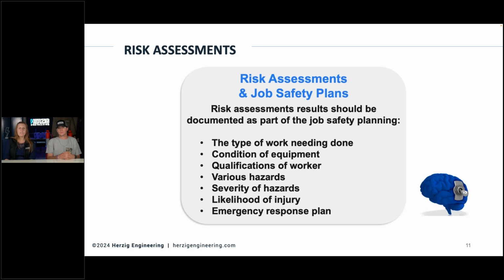And then the severity can change as well. If you're just operating a breaker and everything's installed properly, all the coverings are in place, and the full and complete dead front is still in place, the severity of what you're facing is more than likely lessened. Even if something goes wrong, that properly installed, properly maintained dead front with no openings is going to contain, deflect, or at least limit the amount you're exposed to, versus something that has something wrong with it.